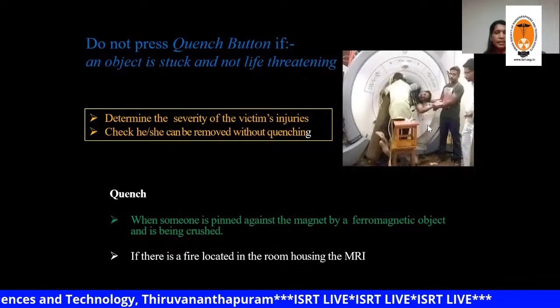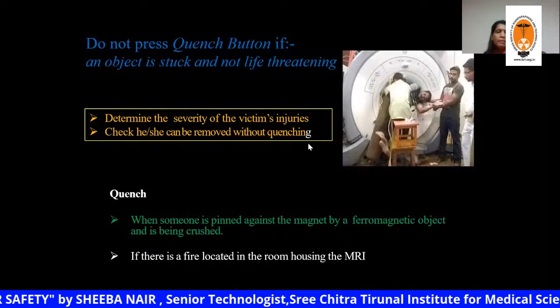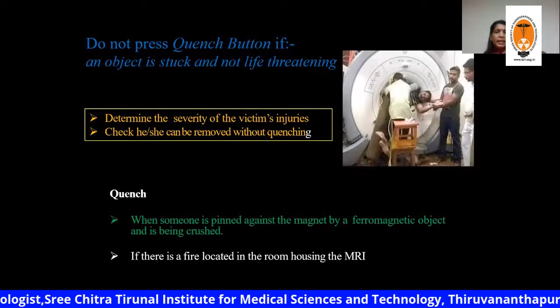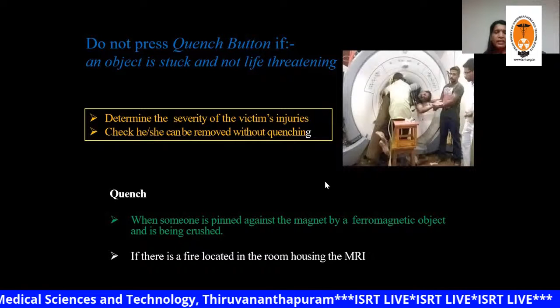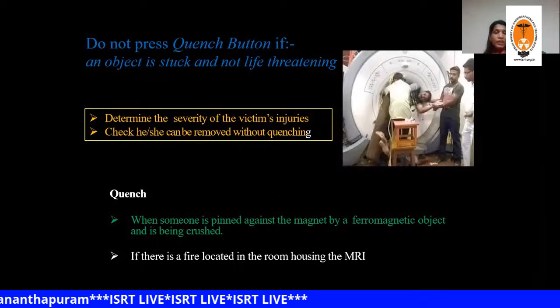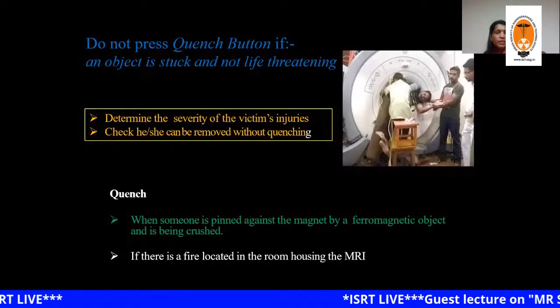Also, if any object gets stuck or any emergency happens in an MRI, when should we press the quench button? That is a concern. First of all, we should assess the severity. If the patient's condition is life-threatening and we cannot wait until the MR engineer comes, then you can press the quench button. But otherwise, if the patient's condition is not that serious or we can wait, then you should not press the quench button. And also, if a severe fire has occurred in the MR scanner room, then also it is recommended to quench the MRI.